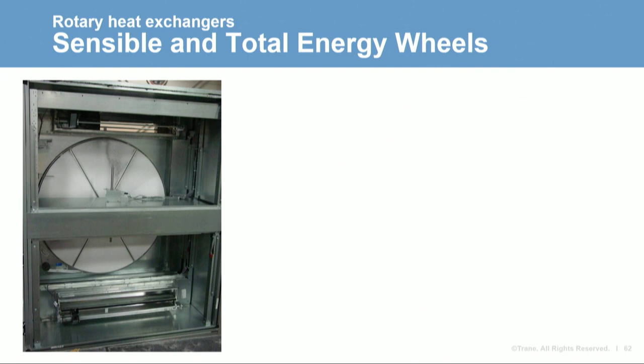As the wheel rotates between airstreams, sensible heat is transferred to the material from the hot airstream and released in the cold airstream. Similarly, latent heat is transferred as the desiccant adsorbs water vapor from the airstream with higher humidity and desorbs in the airstream with lower humidity. This means colder air is heated and drier air is humidified. Capacity control is done with bypass dampers or modulating wheel speed. The wheels experience cross leakage — seal leakage, matrix leakage, and carryover.